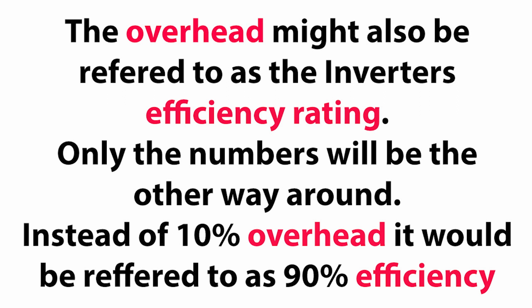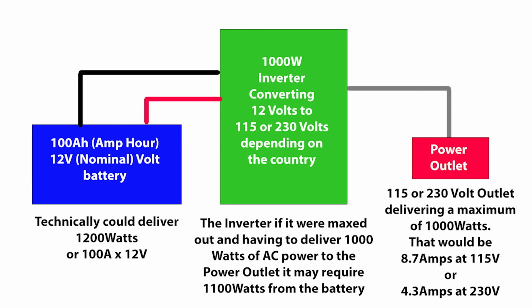The 10% rule of thumb is not a carved in stone overhead rate, but certainly a rate worth using for generalized calculations. Basically, whatever you're pulling from the DC battery in the way of wattage into the inverter, you need to add an additional 10% to, which would bring us to, if we were to max out the entire 1000 watts of 230 volts of AC power from the inverter, the DC power draw on the leisure battery side would be roughly 1100 watts.